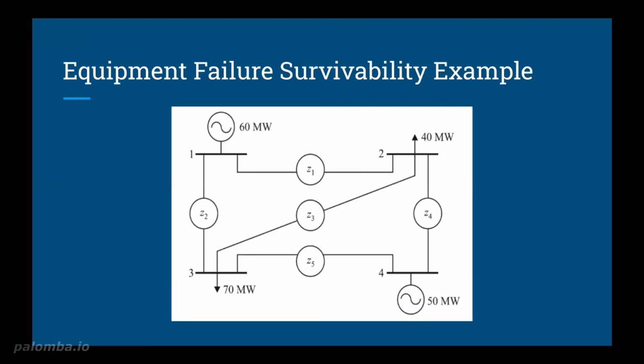And additionally, we're assuming observability and convergence are not going to be an issue. And although these economic challenges are very important and should not be simply brushed aside, I think it's conceivable that one day in the future, these challenges will be eliminated due to economic growth. And as such here, in this example, we consider a hypothetical 4-bus power system in which all digital components share their electrical power system measurements and perform a nearly instantaneous estimation of the power system states and discard bad data. In such a system, it would be possible for the protective relays to act upon the estimation of power system states and their program settings rather than directly upon CT and PT measurements. And we intend to prove here with this example that this could improve system protection.